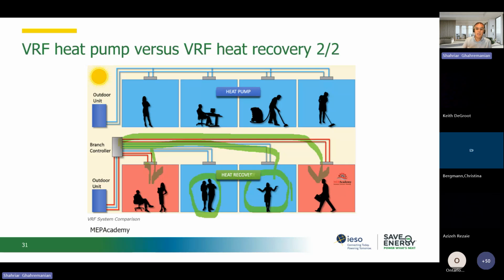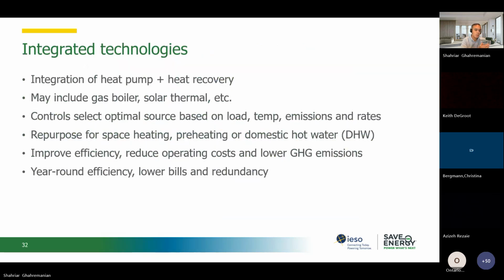So again, that's a good one. But this is for the cases where we need simultaneous heating and cooling, at the same time. Now I want to focus on integrating these two great technologies together, so integrating heat pumps and heat recovery. It can be combined or integrated with any combustion system, like a boiler, a furnace, or even solar thermal systems. We need to have a proper control for sure.